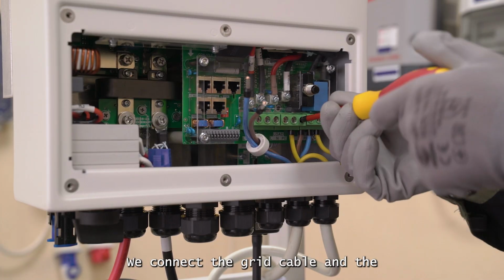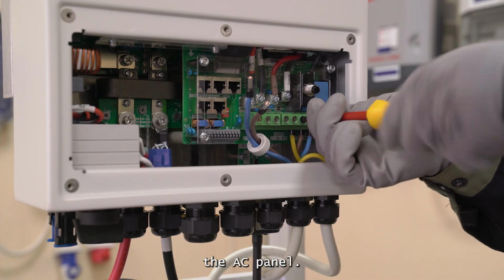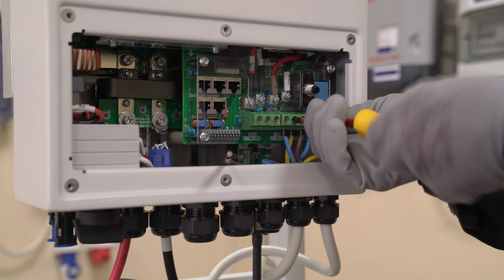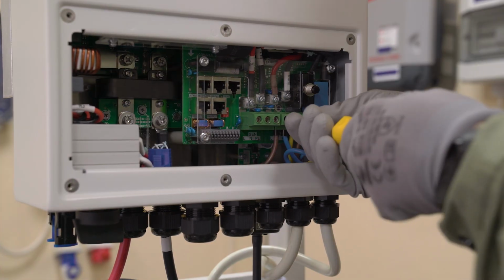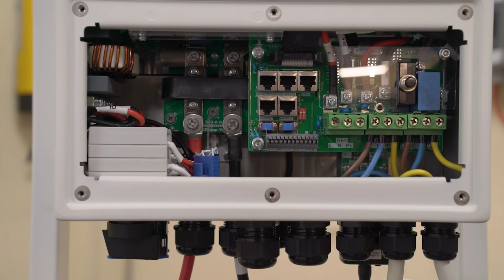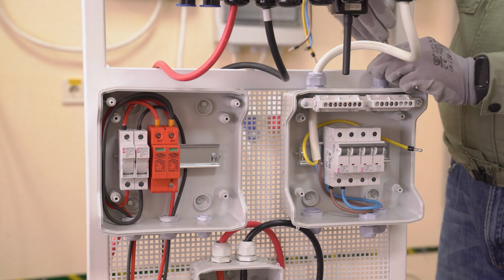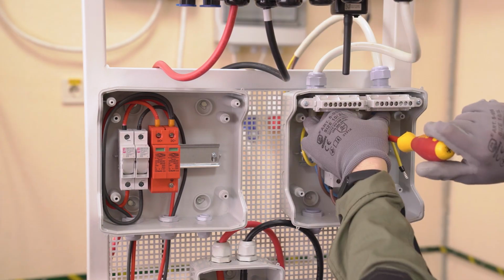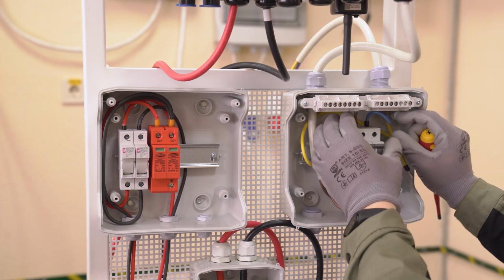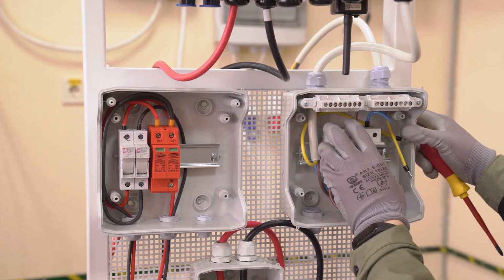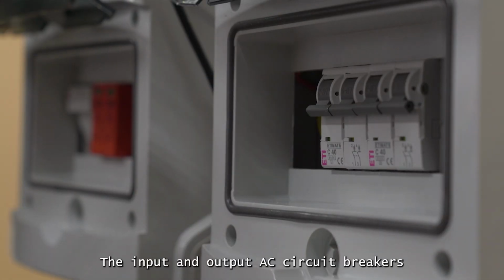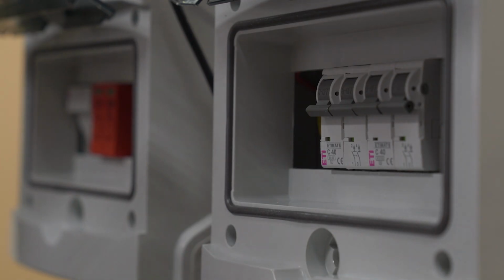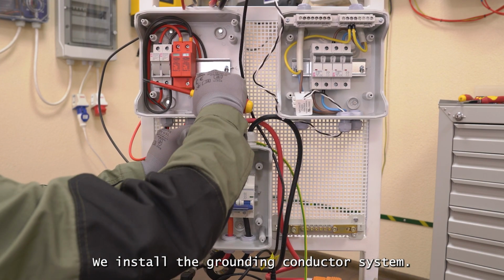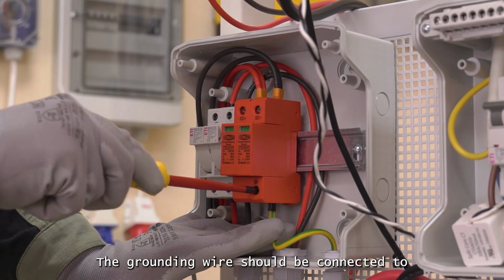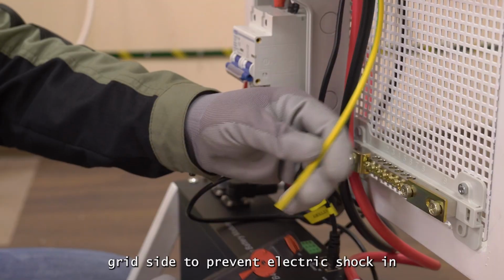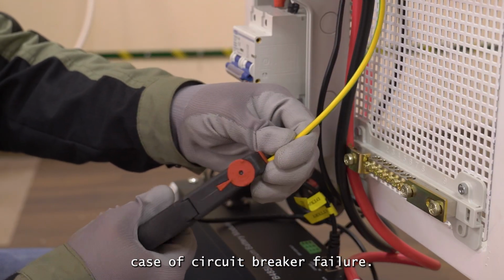We connect the grid cable and the cable that will power the load to the AC panel. The input and output AC circuit breakers should be in the off position. We install the grounding conductor system. The grounding wire should be connected to the housings of all devices on the grid side to prevent electric shock in case of circuit breaker failure.